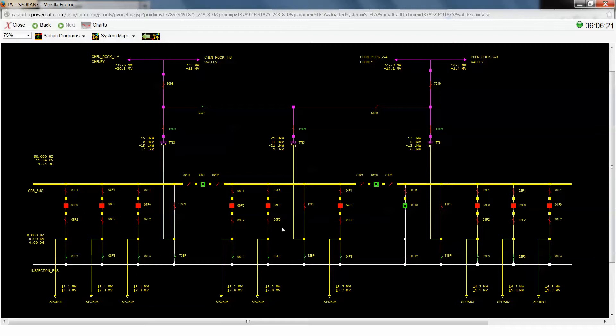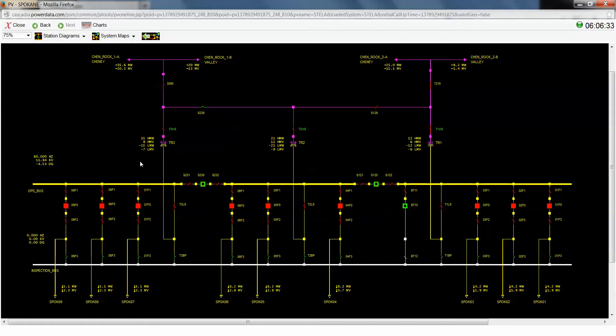So in order to perform our switching, there's a couple of things we're going to have to note. One being that this is actually de-energized, so we're going to have to test this before we do anything else. And the other thing that you'll notice is the low side switch and the bypass switch for this Transformer 3 are both manually operated non-load break switches.